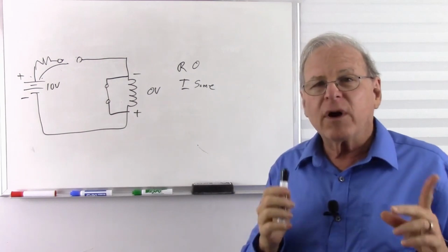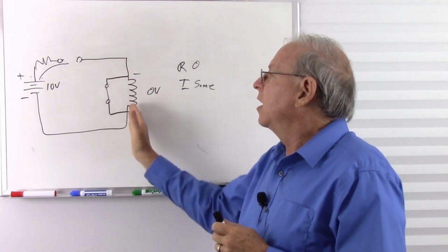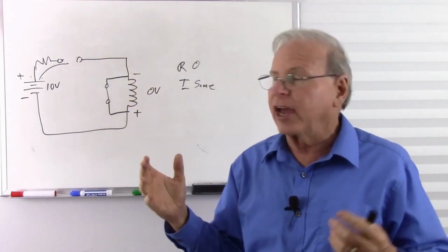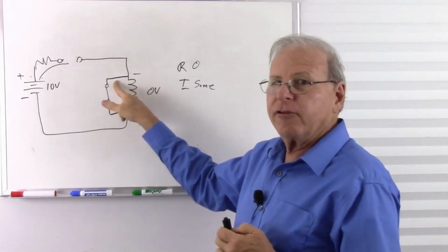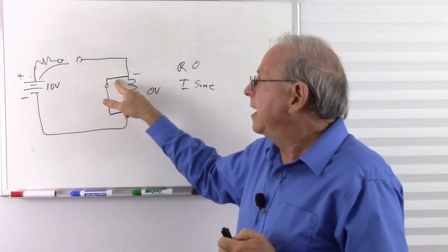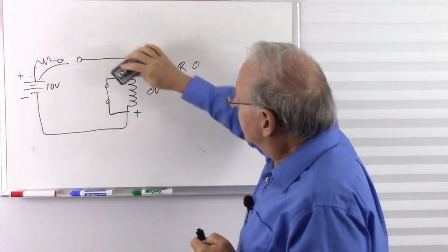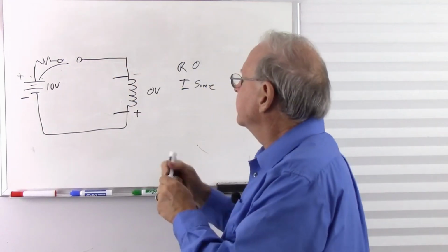So we don't get that voltage spike, and that's why we put a diode in that orientation. Now the question comes up, well, what about the voltage that builds up when this is on the building cycle, or on the charging cycle, if you will? Could we not get dangerous voltages here? We could get higher voltages. It could be a problem. I've never seen this done, but I suppose we could put a Zener diode here.